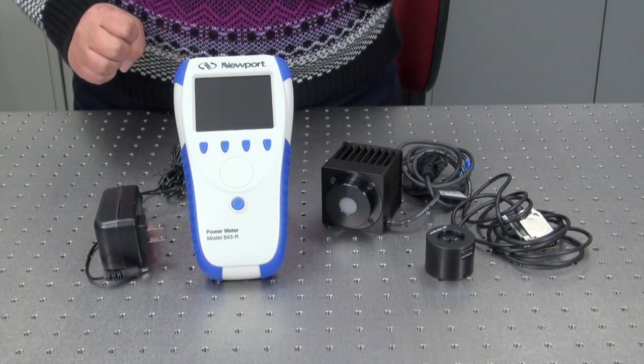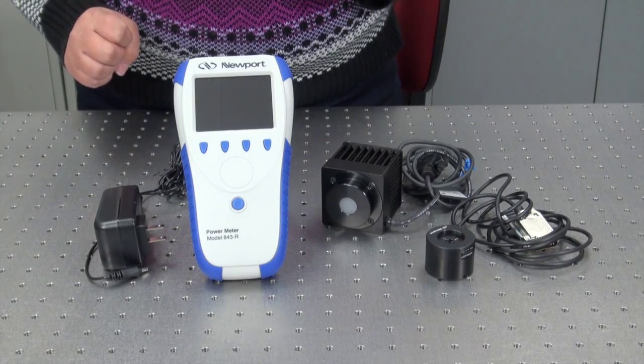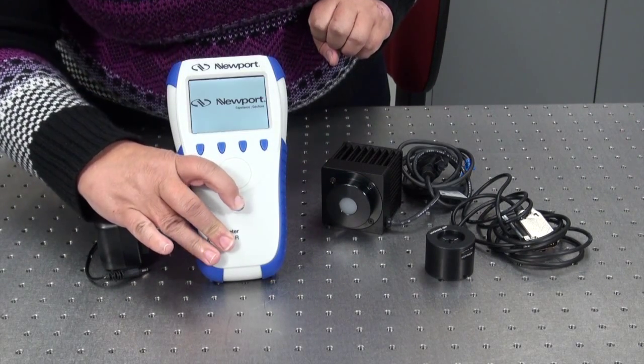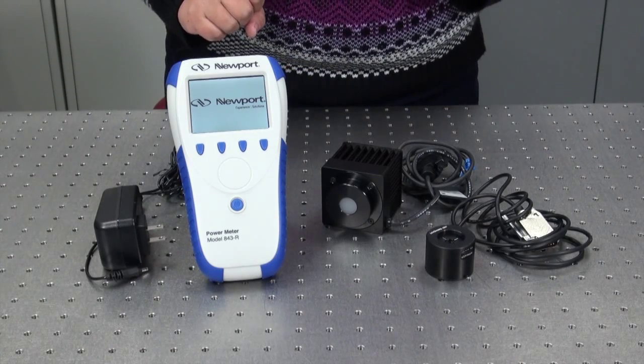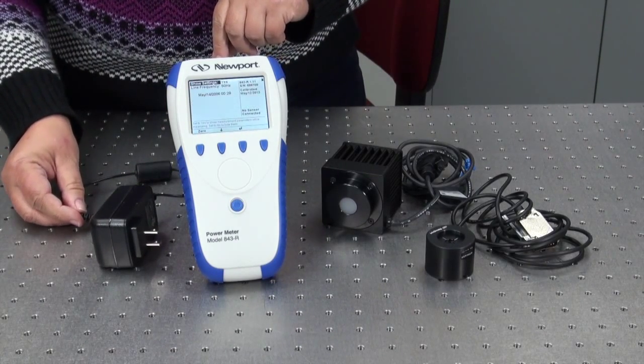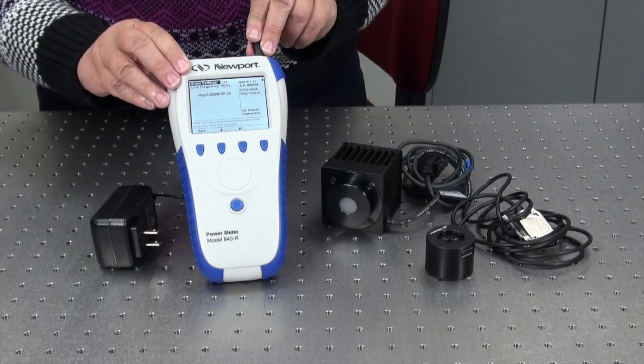Setting up your 843-R power meter for operation is quick and easy. Turn on the 843-R by holding down the blue power button until the monitor screen activates. If the meter is not charged, make certain to plug in the power supply.